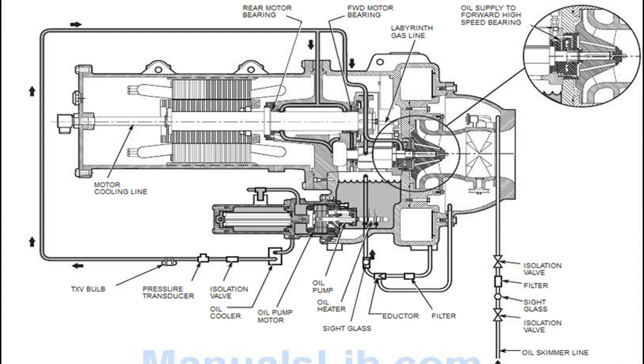The oil is then divided: part flows to the thrust bearing, forward pinion bearing, and gear spray; the rest lubricates the motor shaft bearings and rear pinion bearing. Oil temperature is measured in the bearing housing. As oil leaves the thrust and forward journal bearings, it drains into the oil reservoir at the base of the compressor. The PIC2 (Product Integrated Control 2) measures oil temperature in the sump and maintains that temperature during shutdown, readable on the CVC/iCVC default screen.